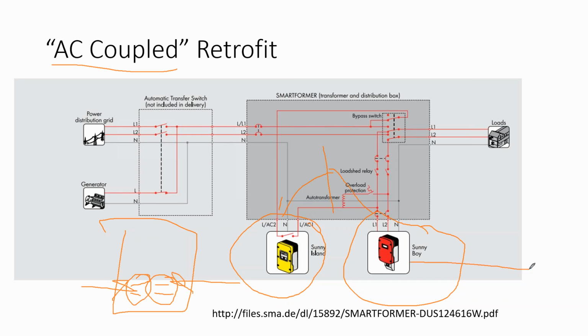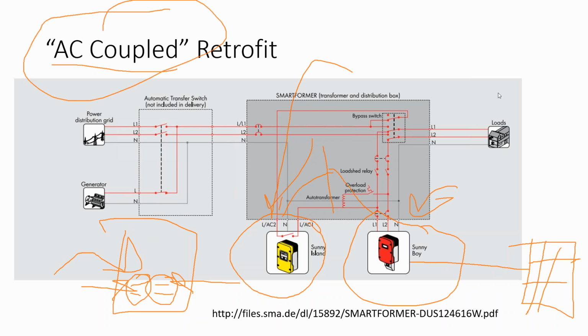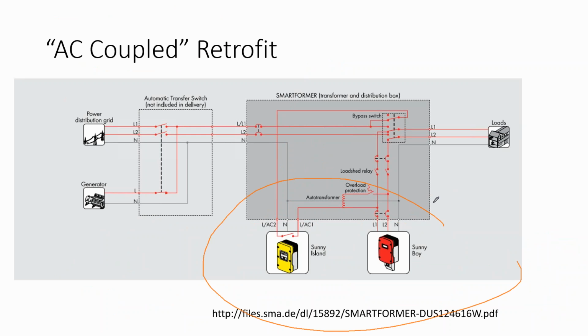And so that might mean that you have an existing home with a solar array on it, and you want to go and add batteries to it. And so you just go and add a battery on its own inverter in parallel to the existing solar array. And that's called AC coupling. And it's allowed. You're allowed to do this. Now, in this case, this is an SMA battery inverter and an SMA solar inverter, and you'll run Ethernet cable between the two so that they can talk to each other.